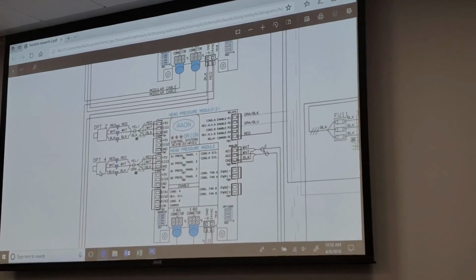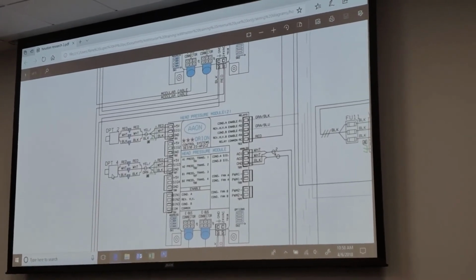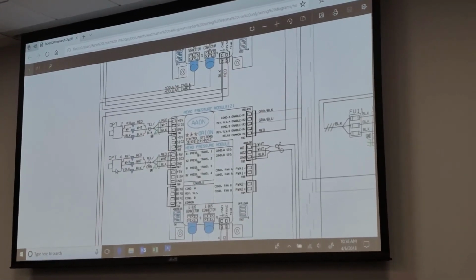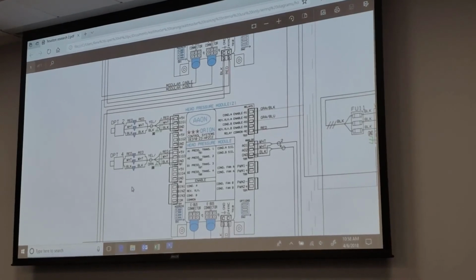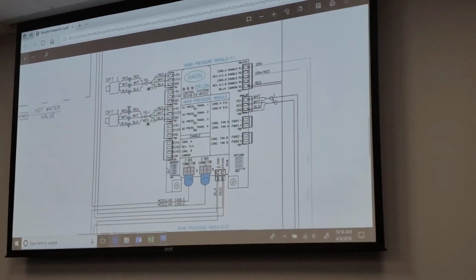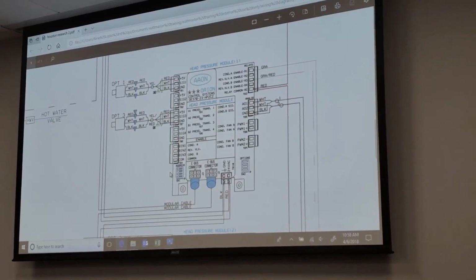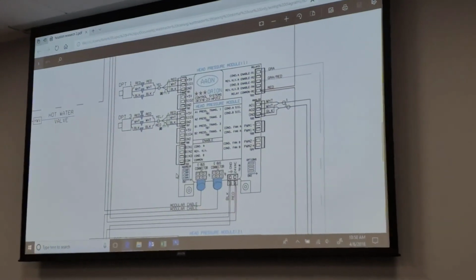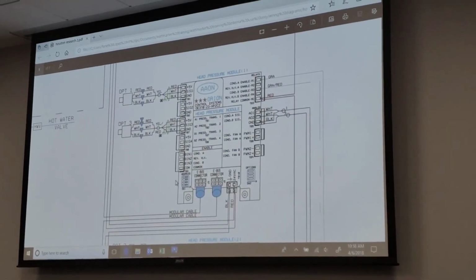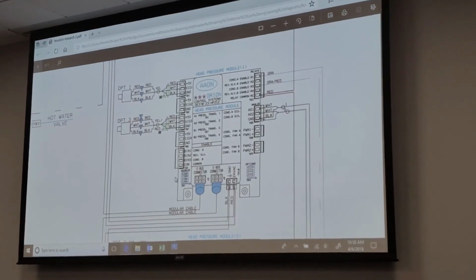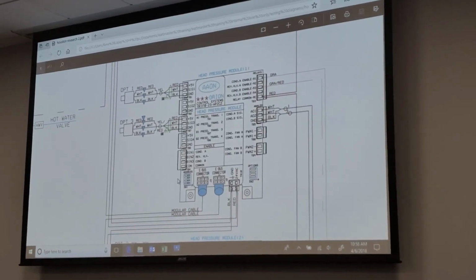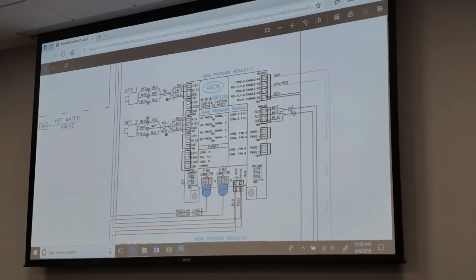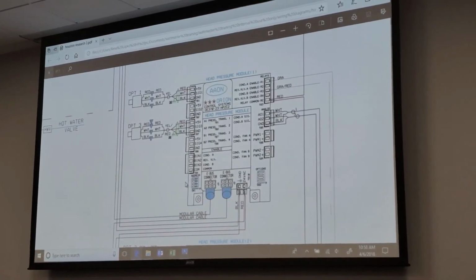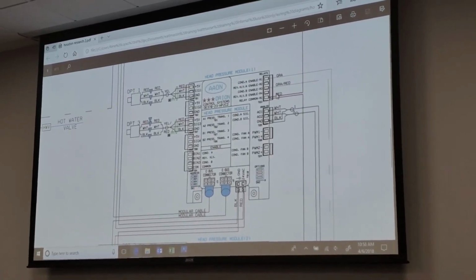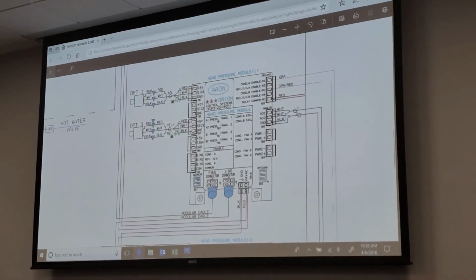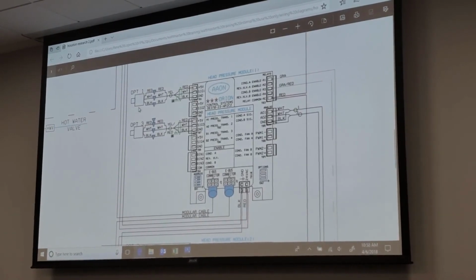That's something that you've got to look at. I'm not saying that you're always going to see it. When you look at staging of compressors, I caught it just because I try to pay attention to how the compressor starts up. Compressor 1 starts up, 1 and 2 start up, then it goes to compressor 3, then number 4. What do the transducers look like? What do the outputs look like? So just paying close attention to how these compressors start up and what relays fire what, I actually picked that up pretty quick.